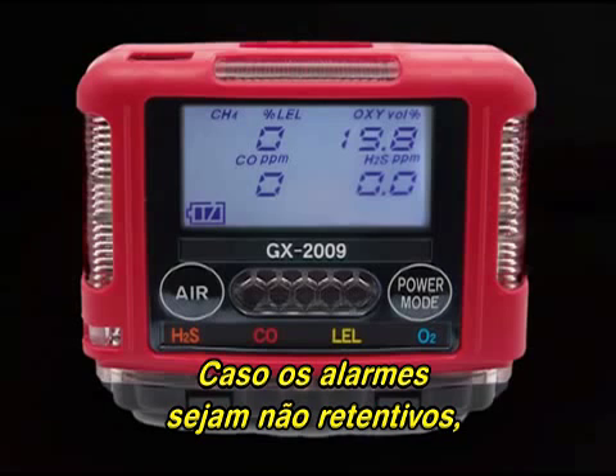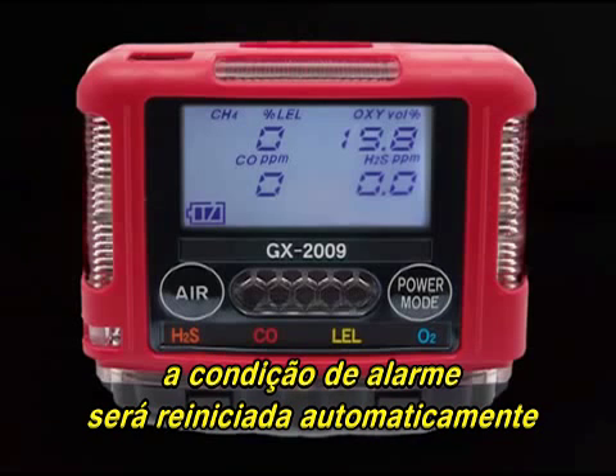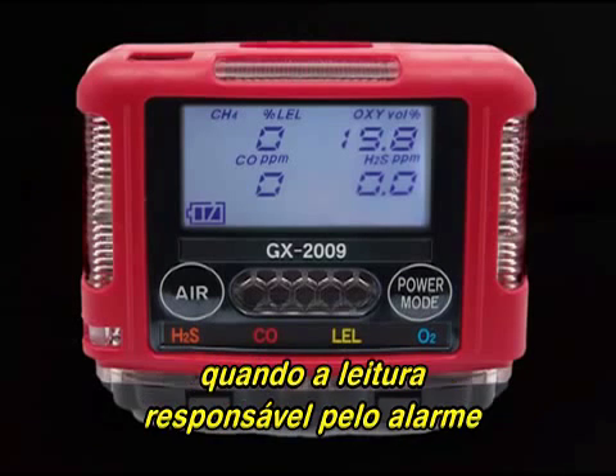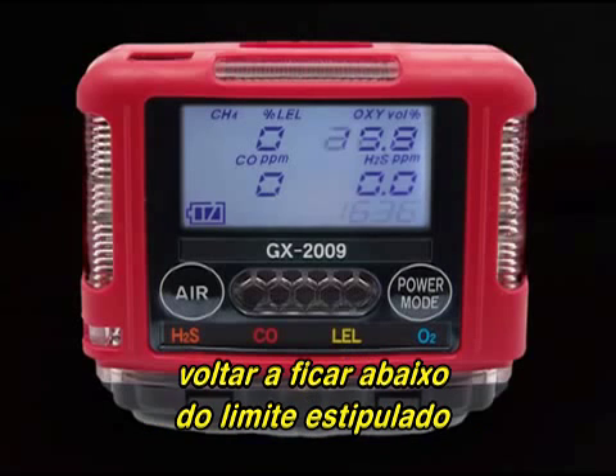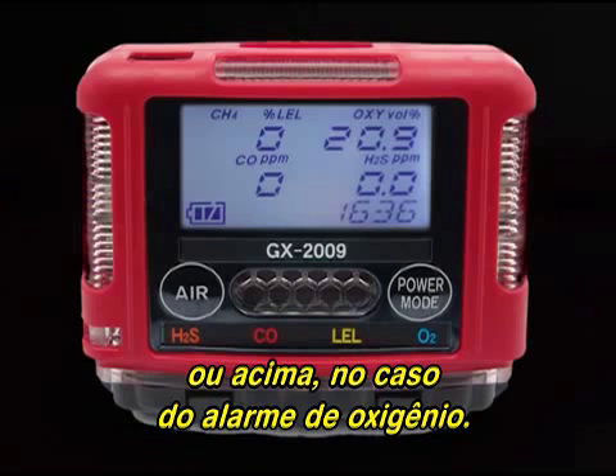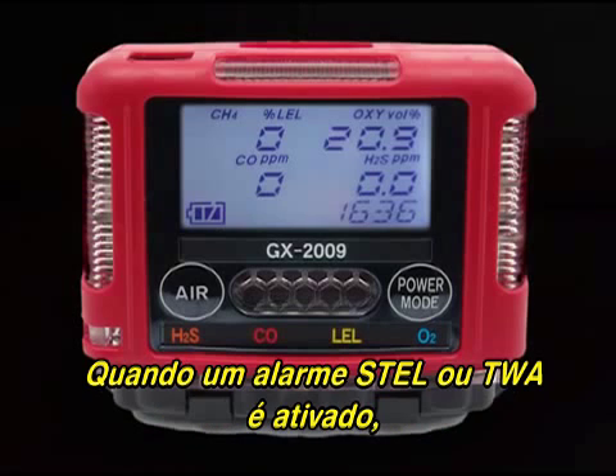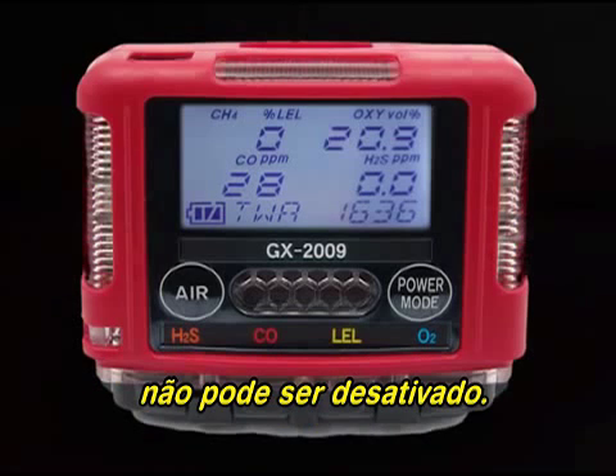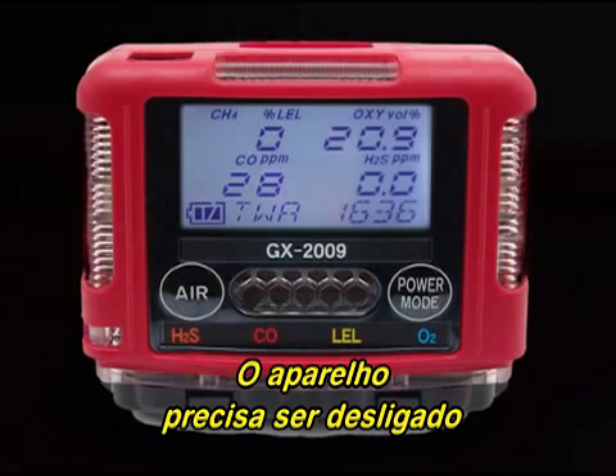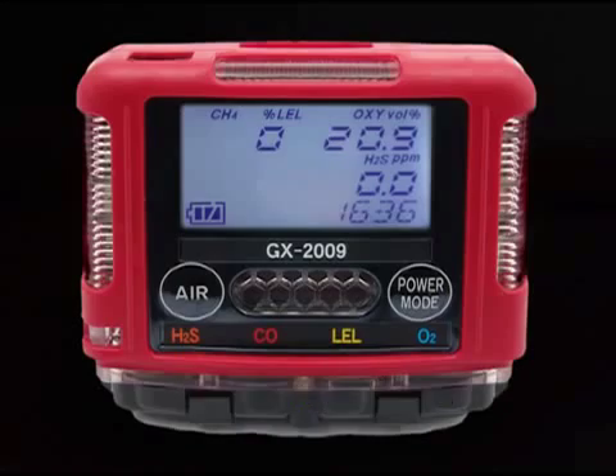If the alarms are self-resetting, then an alarm condition will automatically reset when the gas reading that caused the alarm decreases below the alarm set point or increases above for oxygen. If a STEL or TWA alarm has been activated, it cannot be reset. You must turn off the unit to clear the alarm.